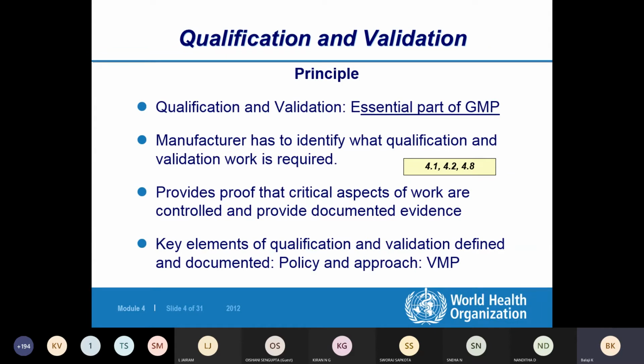Accordingly, the time can vary. There is a deep calculation available in the documents. When you are preparing your presentation, you can identify all these in the autoclave validation practices. There is a formula behind that for how to do the calculation. If it is 121.1, don't consider 121.2. If you put 121.1 for 15 minutes, then the F0 value, there is a terminology called F0 value, will be 15 minutes. If you put 121.2, the F0 will increase, because this 0.1 degree will change the complete data of the F0 value.